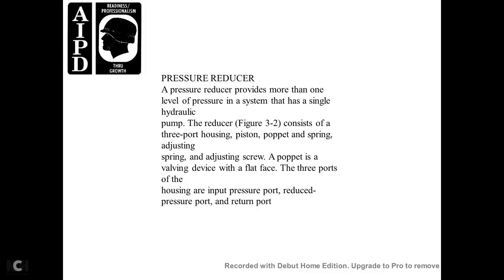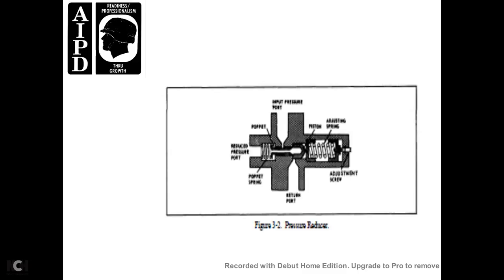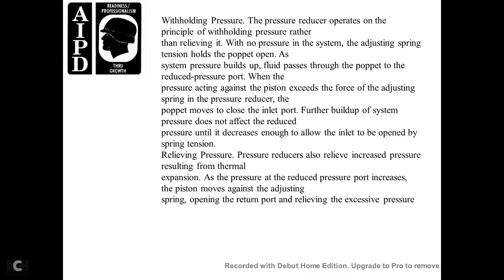Pressure Reducer. A pressure reducer provides more than one level of pressure in a system with a single hydraulic pump. The reducer has a three-port housing, piston, poppet, springs, and adjusting screw. The poppet is a valve device with a flat face. The three ports are input pressure port, reduced pressure port, and return port. The pressure reducer operates on the principle of withholding pressure rather than relieving it. With no pressure in the system, the adjusting spring tension holds the poppet open. As the system produces fluid and builds up pressure, the reduced pressure acts against the piston. As pressure proceeds against the force of the adjusting spring, the pressure with the poppet moves to close the inlet port. Further build-up of system pressure does not affect the reduced pressure until it decreases enough to allow the inlet to be reopened. The pressure reducer also reduces pressure increases resulting from thermal expansion — as reduced-port pressure increases, the piston moves against the adjusting spring, opening the return port and relieving the excessive pressure.